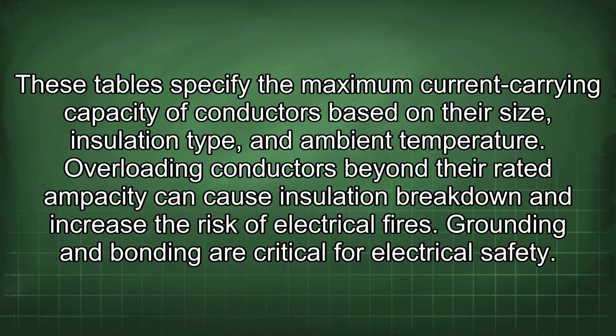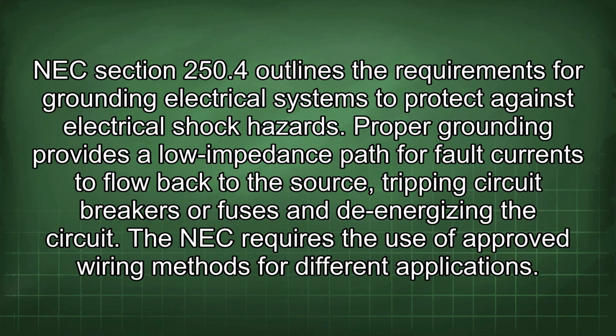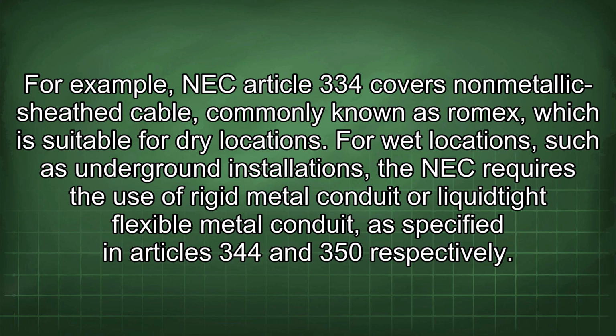Grounding and bonding are critical for electrical safety. NEC Section 250.4 outlines the requirements for grounding electrical systems to protect against electrical shock hazards. Proper grounding provides a low impedance path for fault currents to flow back to the source, tripping circuit breakers or fuses and de-energizing the circuit. NEC requires the use of approved wiring methods for different applications. For example, NEC Article 334 covers non-metallic sheath cable, commonly known as Romex, which is suitable for dry locations. For wet locations, such as underground installations, the NEC requires the use of rigid metal conduit or liquid-tight flexible metal conduit, as specified in Articles 344 and 350 respectively.